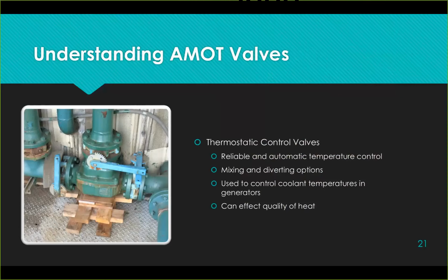So if you're looking for a high quality of heat, when I say quality of heat, if you're looking to have 190, 195 degrees heat sent out because of the building you're serving, you may want to consider either replacing and/or retrofitting an existing valve to make sure that it doesn't bleed by so you can get a better quality of heat. And that is, again, a costly adventure here.